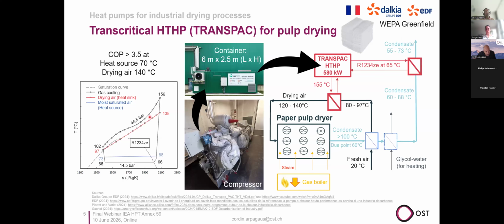And here the transcritical cooling of this HFO refrigerant allows to heat up the air to high temperature. So it's a suitable solution, this transcritical technology, to heat up an airstream with large glide. The COP that is achieved is higher than 3.5, so it seems to be an economic case. And I would expect that this technology gets further implemented into the market.